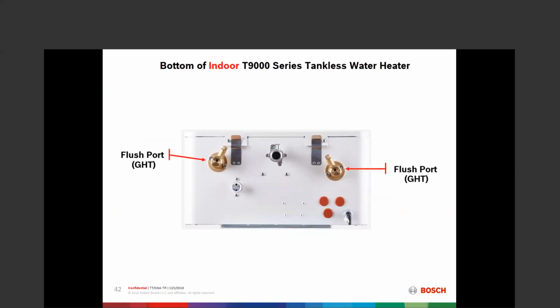Those flush ports have their own built-in valves. Those are those knobs on the ends. You can see on the end of the stub here. That's where that valve is. We're going to turn that to open the flush ports. Condensate drain. Condensate is managed by a condensate collector, which is a siphon. So it's going to fill that siphon and then dump it periodically. It's not a constant drip of condensate. And in that, there is a breather hole external of the cabinet. So when we're connecting to that, we don't want to get some pipe dope in the breather hole. We don't want to get tape around it. We just need to catch a couple of threads with our PVC onto that connector.